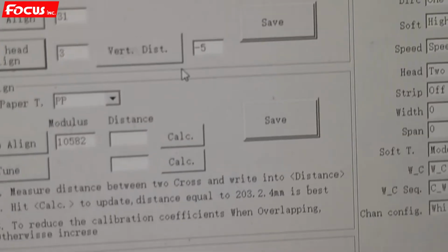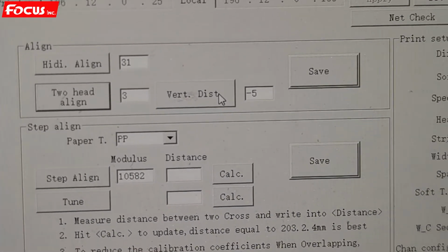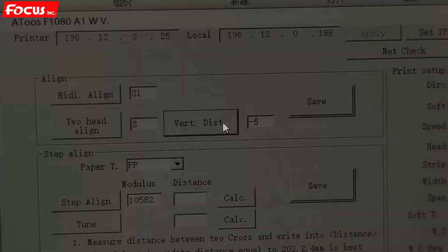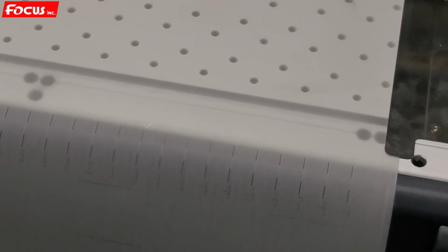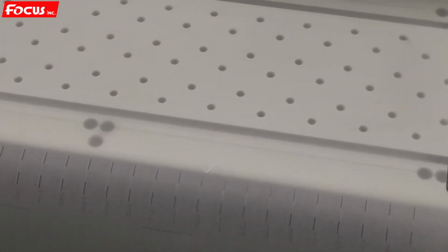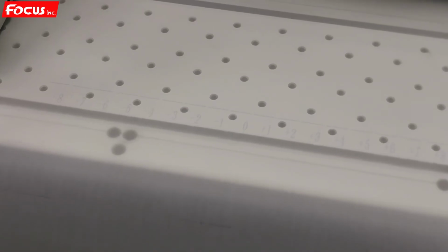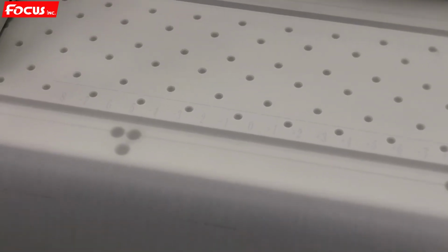Then we go to do the vertical distance test. We press vertical distance test calibration. Then the printer starts to print out a vertical calibration picture out. Here we also check if 0 is closed. So from these lines, we can clearly see that 0 already closed with each other. It's the best. And -1 and +1 is not good.